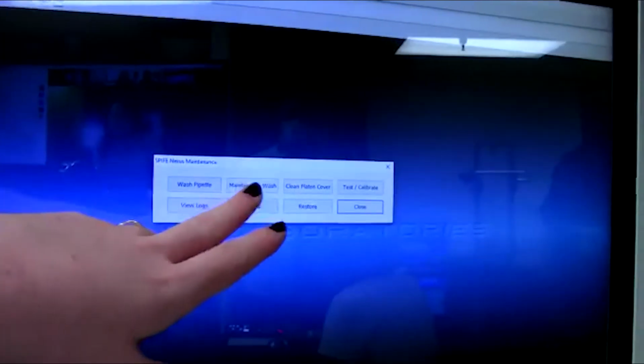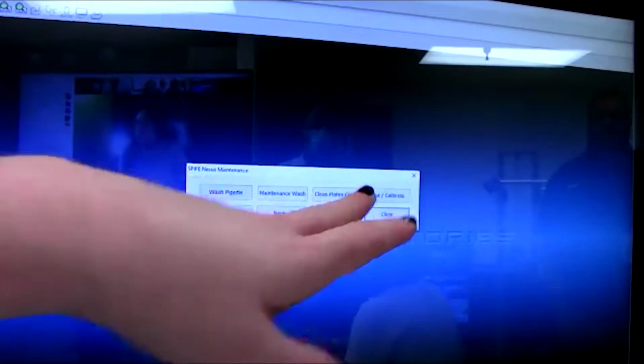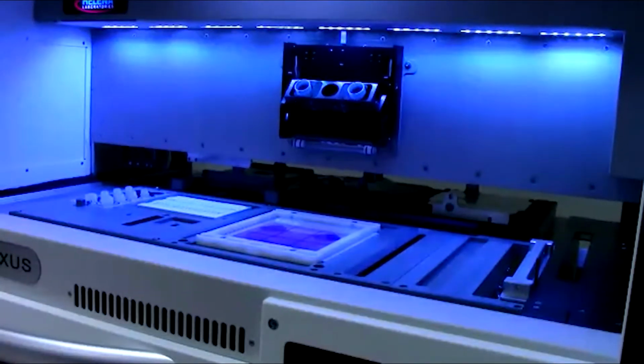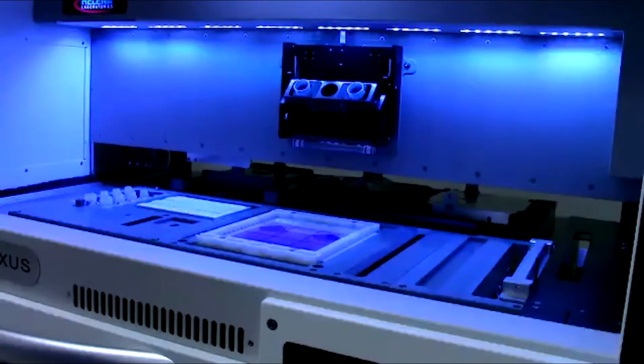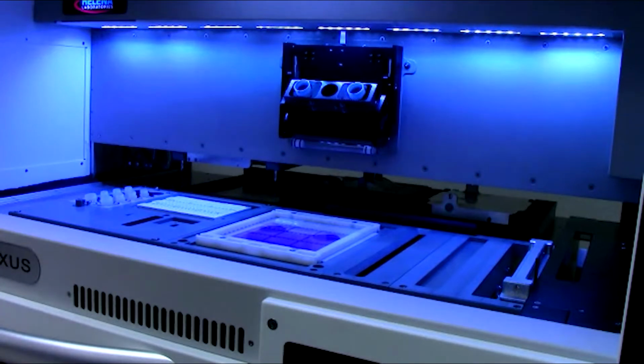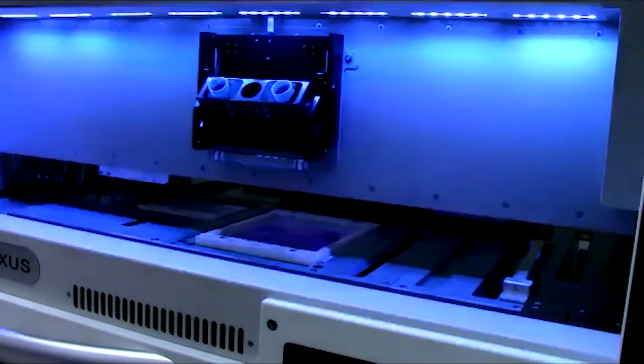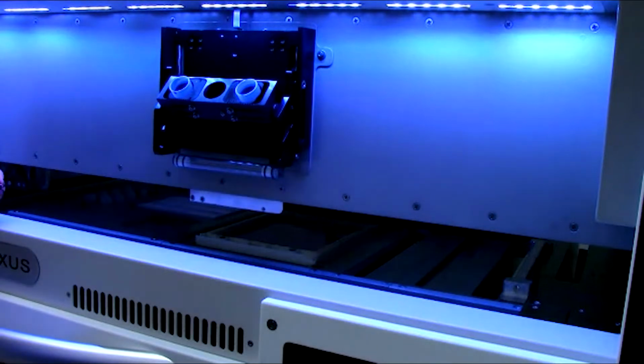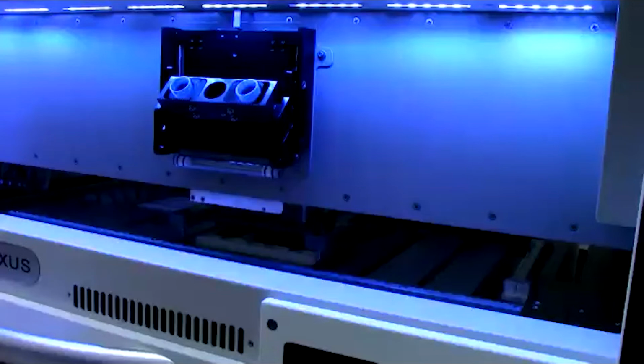So in our maintenance menu here, we have our clean platen cover option, which will bring forward that platen cover. Go ahead and click it down. It brings forward the platen cover so you can then remove it and wipe down the electrodes, which will begin to soot after a while, just like they do in the SPIFE Touch. And this is just a once a week maintenance, just to make sure that you don't end up getting more resistance during your electrophoresis steps.